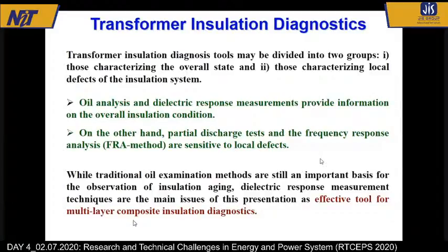Now, whenever we do the test, first of all, we have to understand whether we are trying to find out the local fault or the global condition. That means overall insulation. For example, if we are interested in the second paragraph in green color, there are tests, for example, partial discharge test. Nowadays, frequency response analysis to find mechanical local defects. But if we do the oil analysis, as I have already explained, or the one that I am going to explain, dielectric response measurement, they will not give you the local defects. They will give you only the global information. That means overall insulation condition.